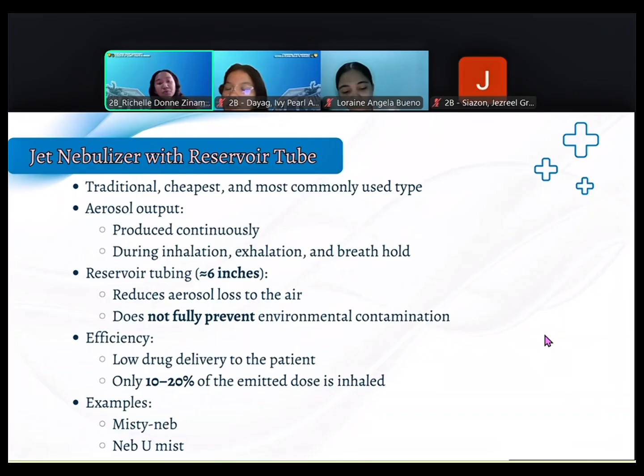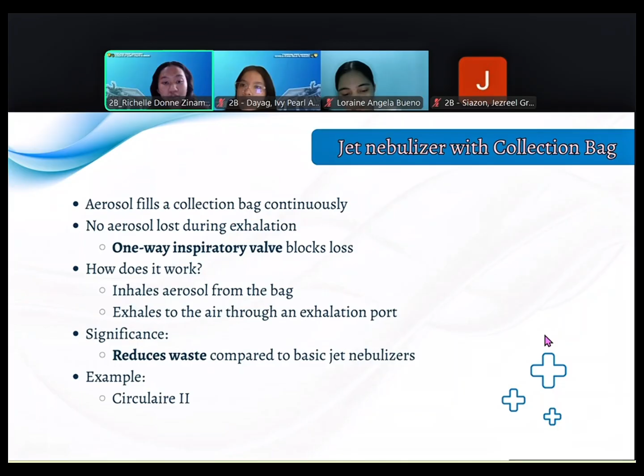For the jet nebulizer with collection bag, the aerosol continuously fills a collection bag, and there is no aerosol loss during exhalation. A good feature of this is that it has a one-way inspiratory valve which blocks loss. So how does it work? The patient inhales aerosol from the bag, and exhales to the air through an exhalation port. The significance of this type is that it reduces waste compared to basic jet nebulizers. And an example is the Circulair 2.